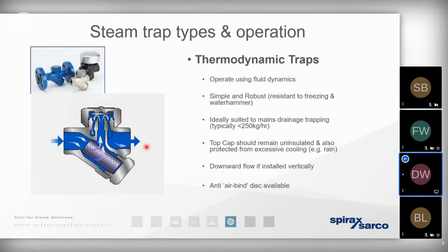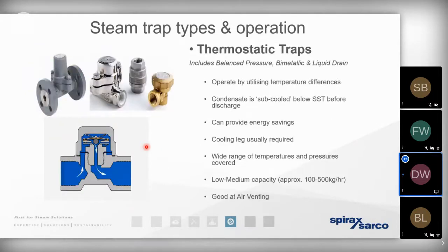Very, very popular on steam distribution networks. We'd never encourage you to use this type of trap at the process itself. Simply got too low a capacity. Another common trap type is what we refer to as the thermostatic trap. It works on the temperature difference between the steam and the condensate. So that means we need to allow the condensate the opportunity to cool down. We need what's referred to as a cooling leg between the process or the distribution pipe work and the steam trap. And that cooling leg needs to be unlagged.